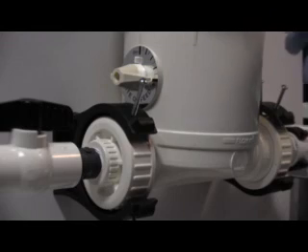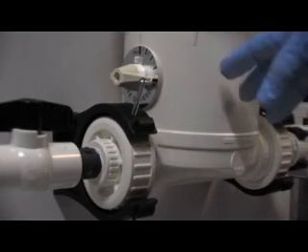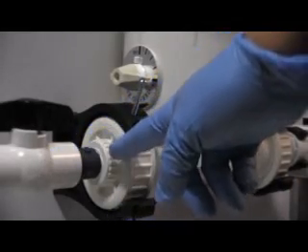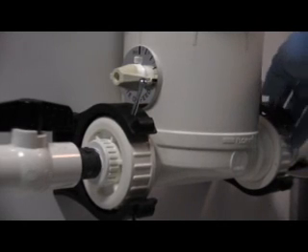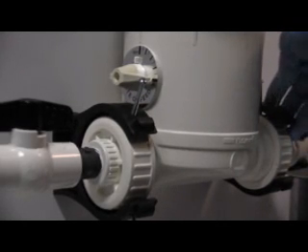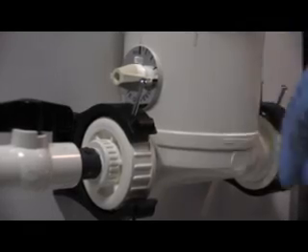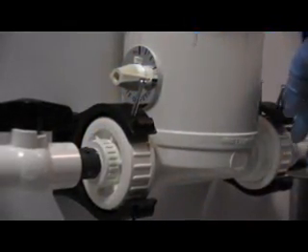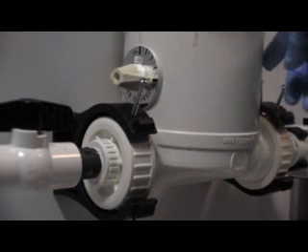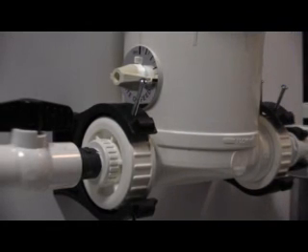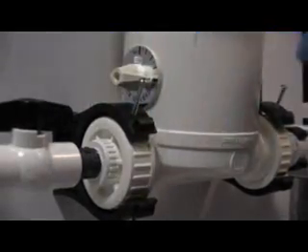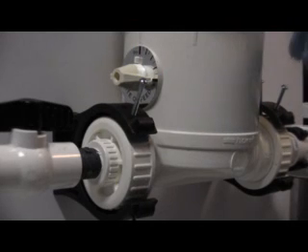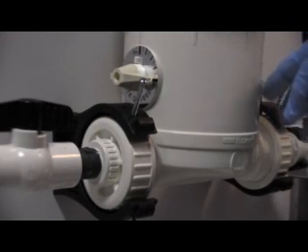Because this unit requires a 20 psi pressure drop in order to function correctly. So that means that on the inlet pressure, if you're at 30, then you cannot have more than an outlet pressure of 10 psi. So if I have an inlet pressure of 30 and an outlet pressure of 25, 30 minus 25 is a 5 psi differential pressure. Not good. What if I have a 10 psi outlet? 30 minus 10 is 20 psi. I have the minimal needed for this unit to work correctly.